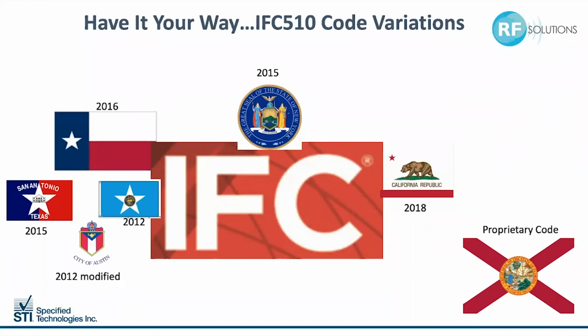Florida has not adopted IFC 510, even though they have adopted ICC codes for construction, plumbing, mechanical standards, and for residential buildings. Instead, Florida has written their own code requiring all commercial buildings to have systems installed, if required, by January 1st, 2022, and for all residential buildings to meet a deadline of January 1st, 2025.